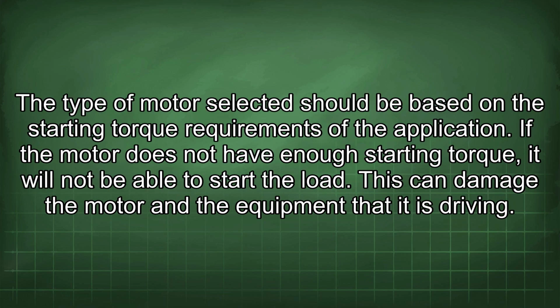The type of motor selected should be based on the starting torque requirements of the application. If the motor does not have enough starting torque, it will not be able to start the load. This can damage the motor and the equipment that it is driving.